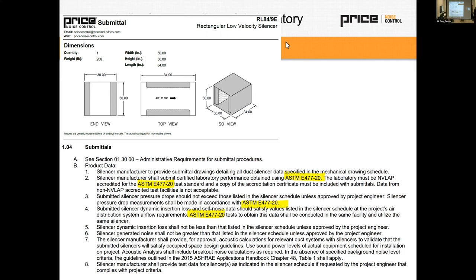Chris, we have another question in the chat. Okay. Is the acoustic media in silencers always in the vertical orientation? Good question. So for rectangular silencers, typically the acoustic media is in the vertical side baffles as depicted here. So these baffles on the side contain acoustic media. It's really hard to do with the mouse, so I'll use this. Circular silencers, elbow silencers, and other types of silencers will have media on all four sides or on the top or bottom. But it really depends on the type of silencer and where that acoustic media is located. But primarily on a rectangular silencer, it's usually only on the sides in the vertical.